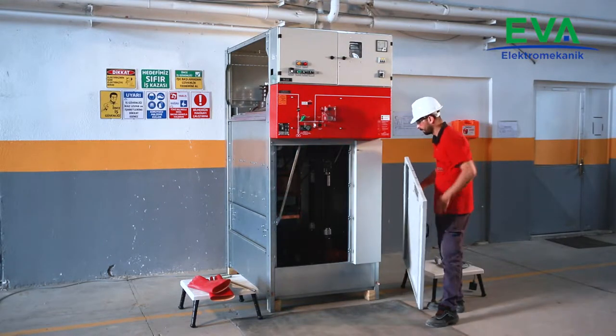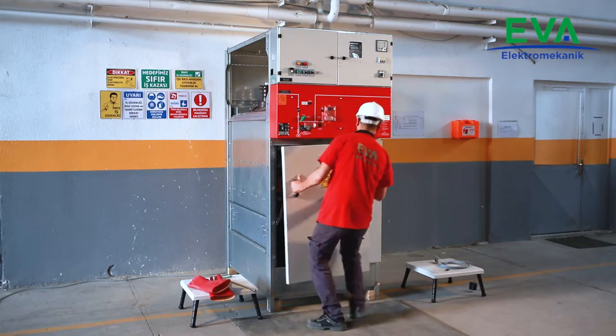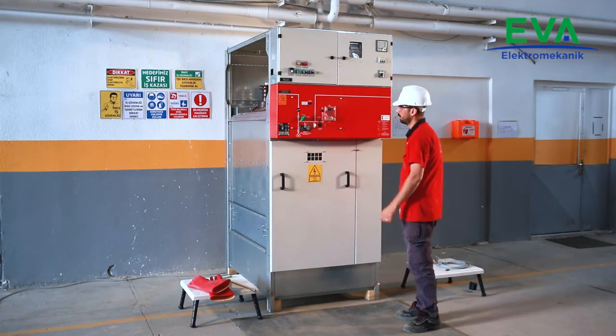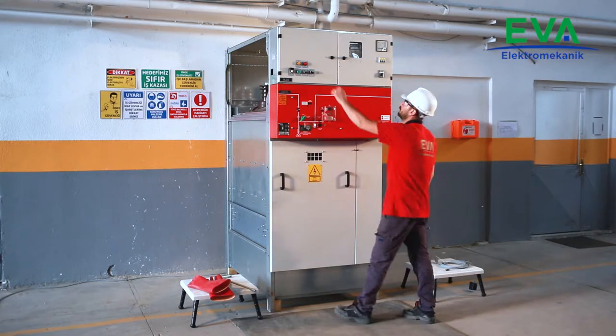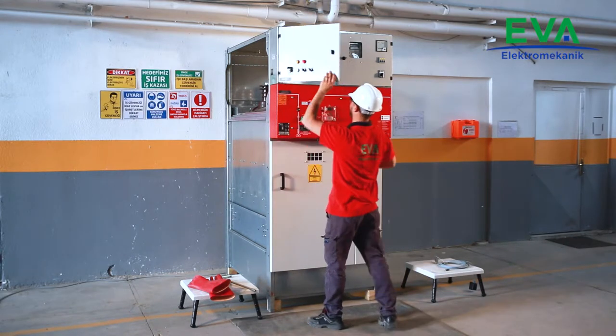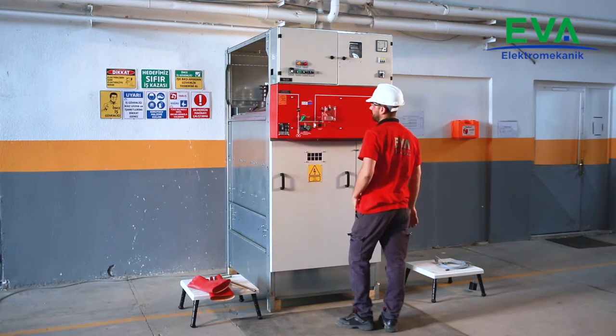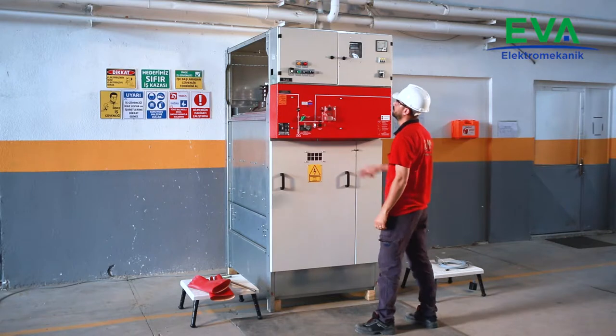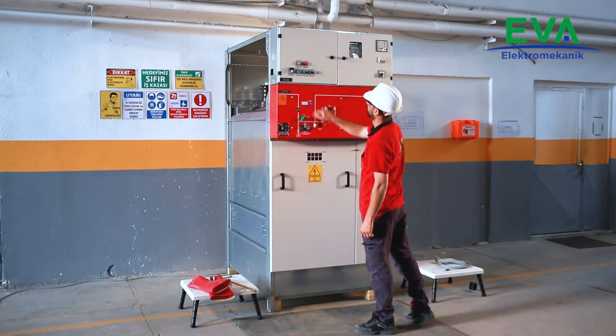Close the cover of the current voltage transformers compartment. Make sure that the auxiliary supply of the cubicle is energized. Check the gas pressure level of the load break switch from the manometer and indicator lamps. It shall be in normal state.